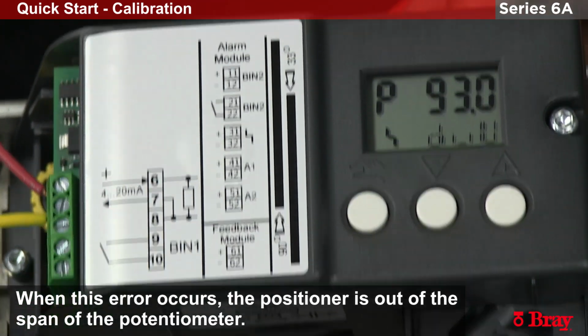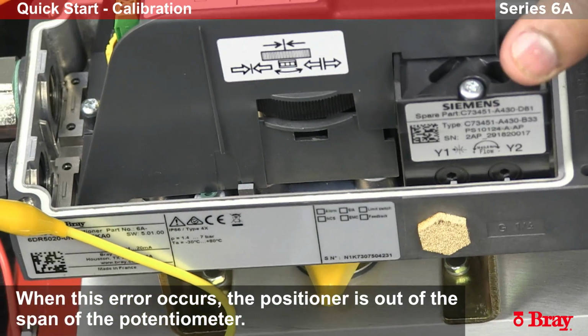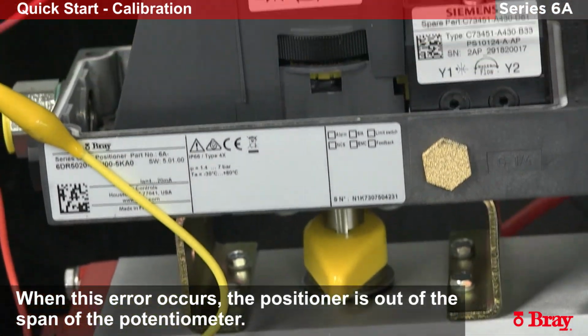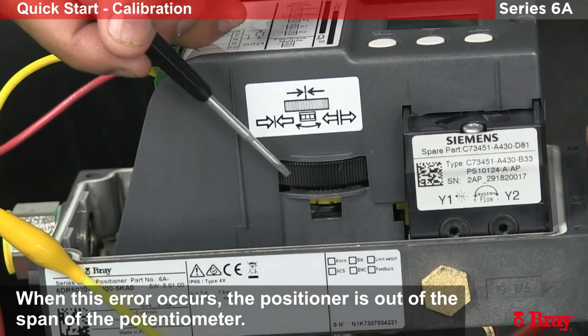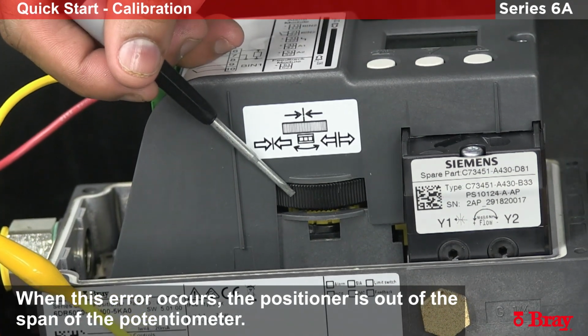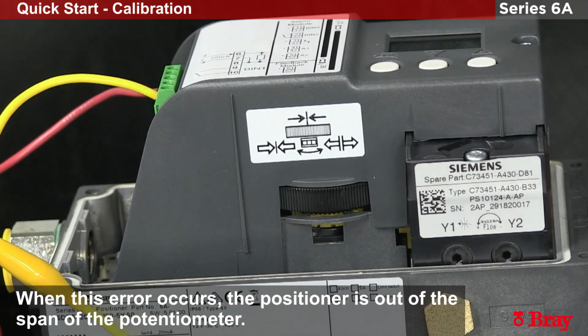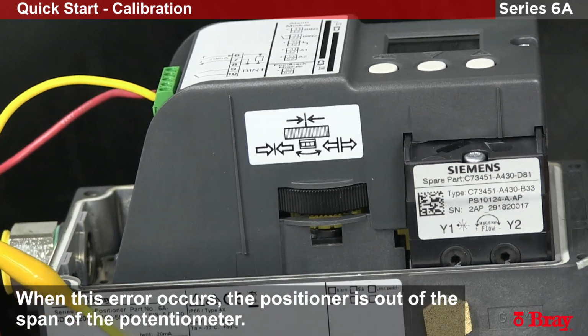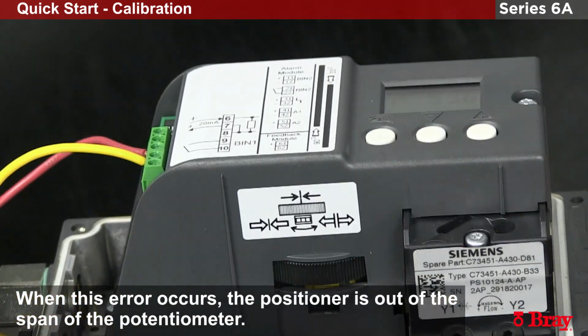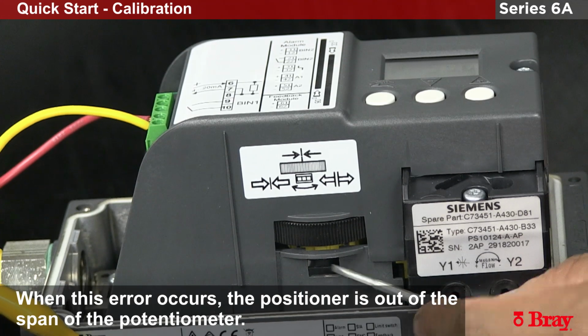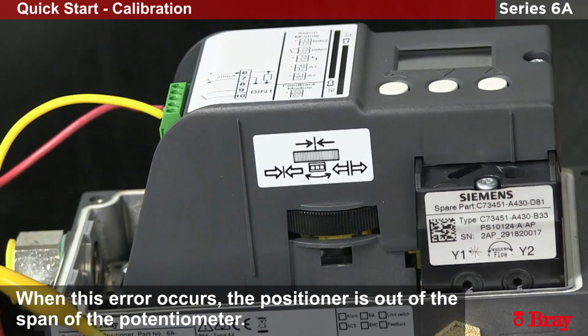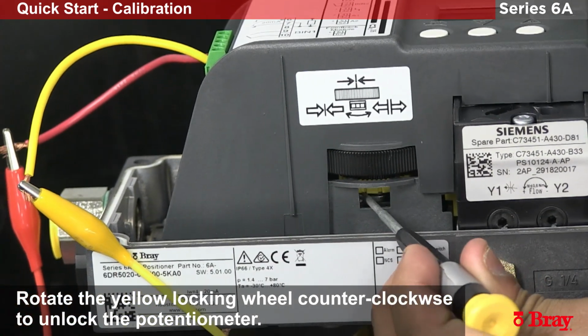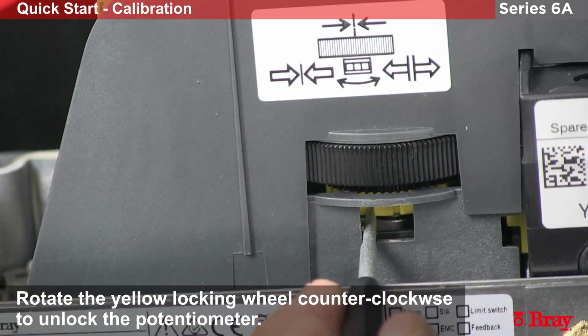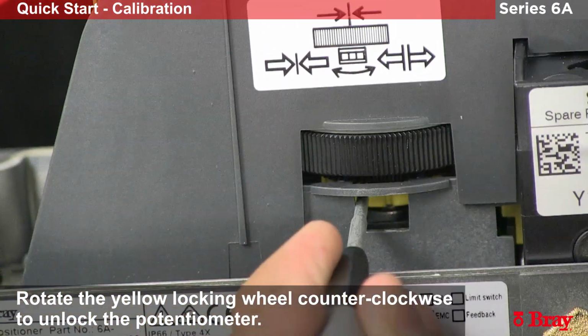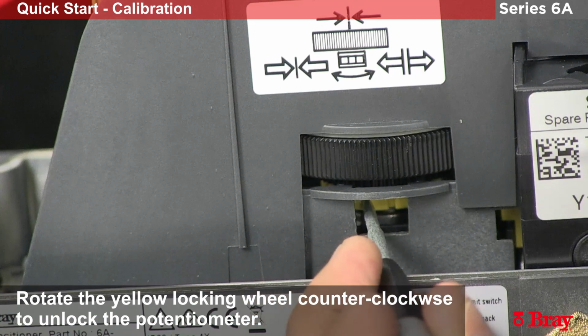What we need to do here is adjust the clutch to bring the span back in so the potentiometer can read the valve. To do this, we will go to the clutch mechanism found on the side of the positioner. This is the clutch wheel. We will adjust this clutch wheel to bring the actuator back into span. The first thing we're going to have to do is unlock the clutch. This small access window here will let you stick a flathead screwdriver where you can access a yellow wheel. We'll move this yellow wheel counterclockwise to unlock the potentiometer.